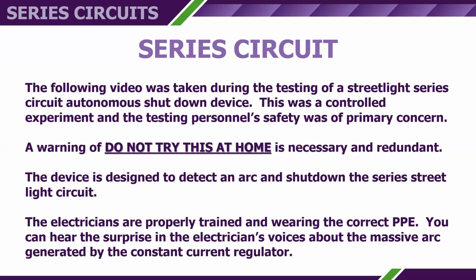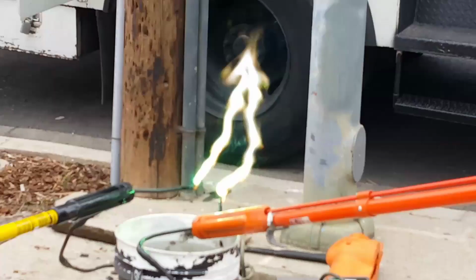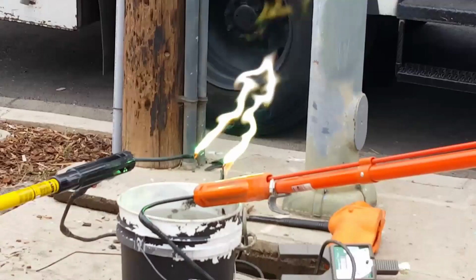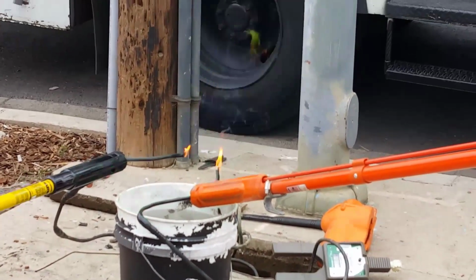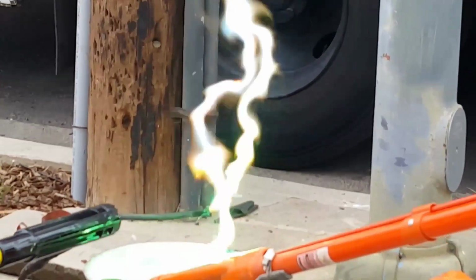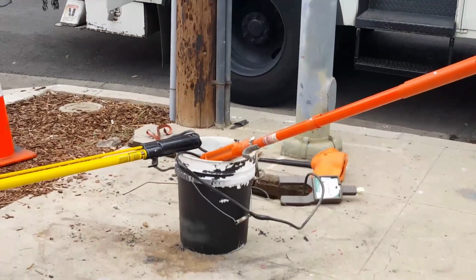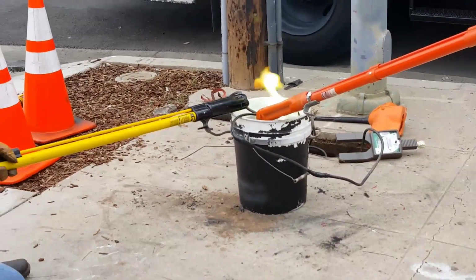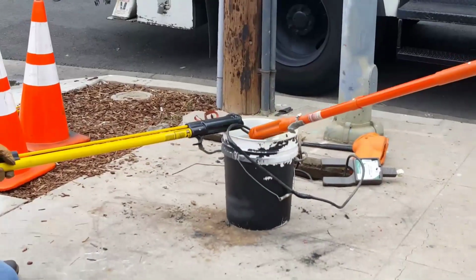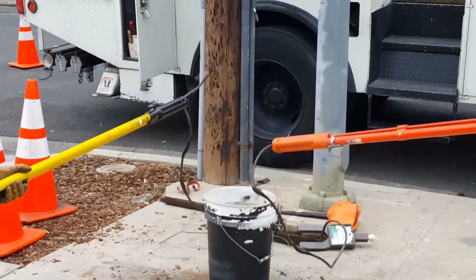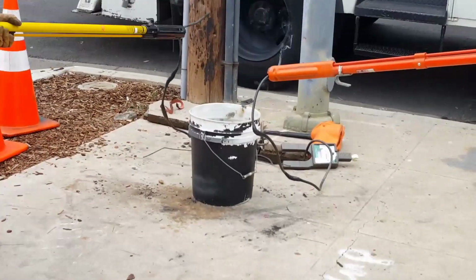Electricians are properly trained in wearing the correct personal protective equipment. You can hear the surprise in the electricians' voices about the massive arc generated by the constant current regulator. This is what happens when you open a constant current regulator. That's the arc. You can see it right there. So imagine opening an energized series circuit and having one of those between your two hands.